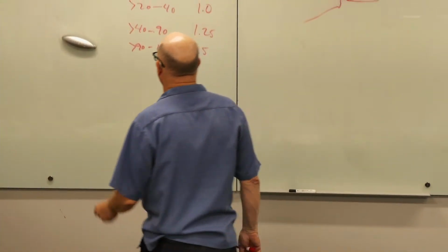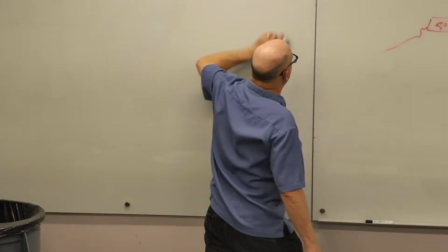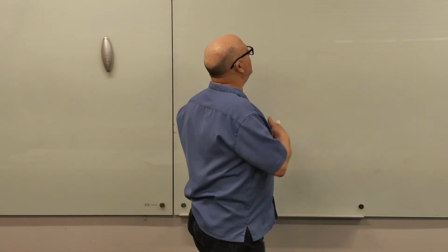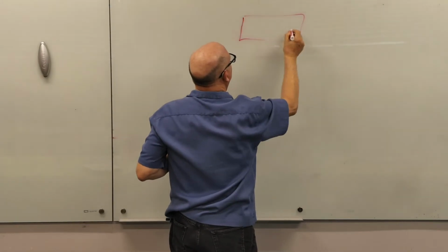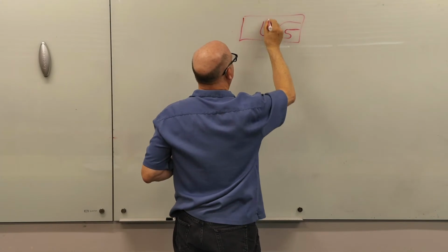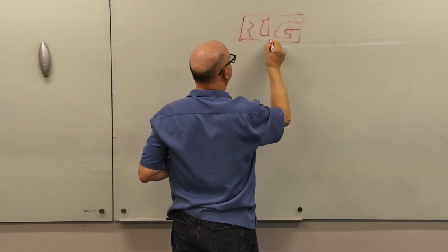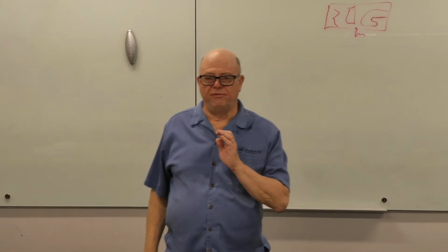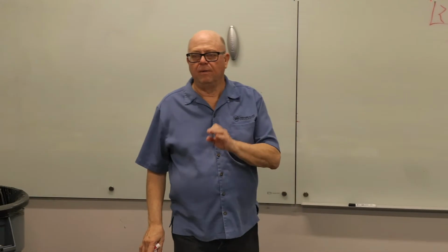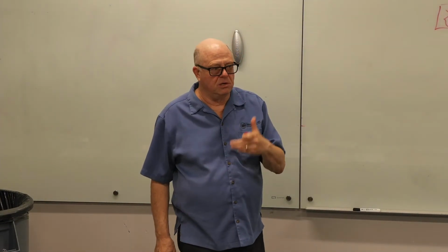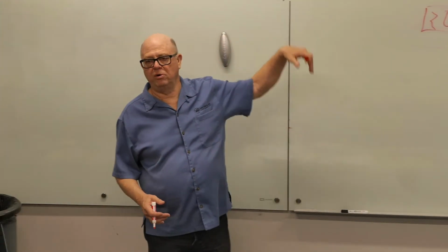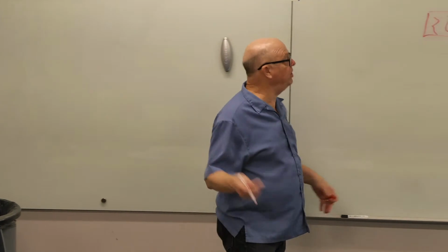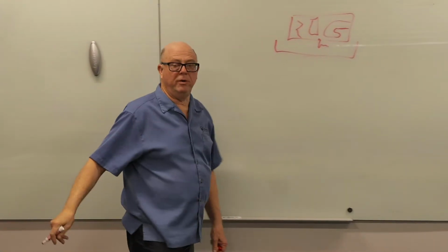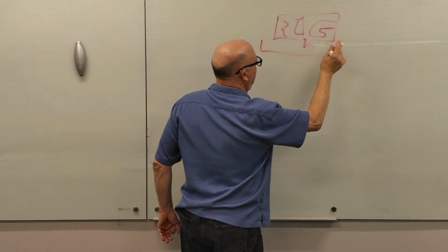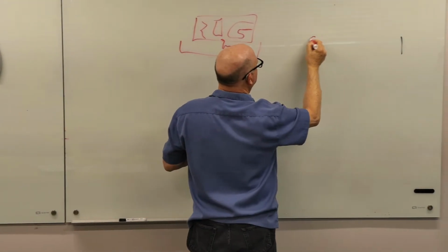Okay, one more plumbing code thing. If you're going to put a fan coil unit above a ceiling, you got a cooling coil, you got a filter, you got a condensate drain, right? If you're going to put that above a ceiling, there's 3 ways to meet the drain requirement to avoid an overflow into the space. One thing you can do is put an auxiliary drain pan under it. That's legit. Almost all of these are also going to have, if I blow it up, this little opening is usually 2 inches.